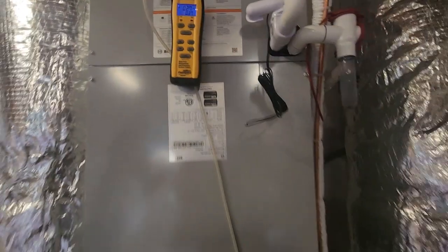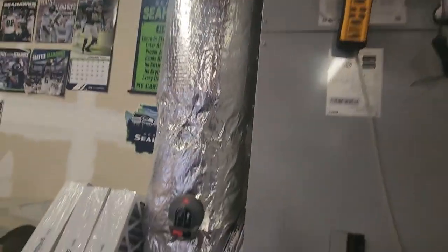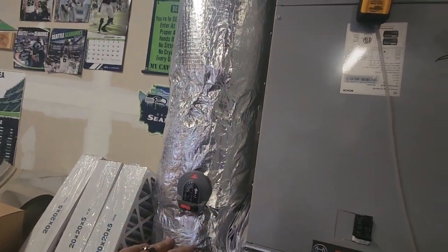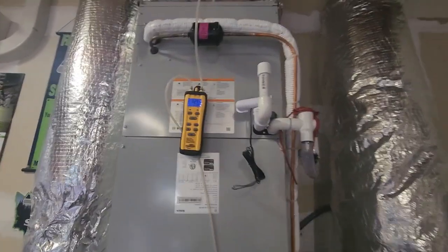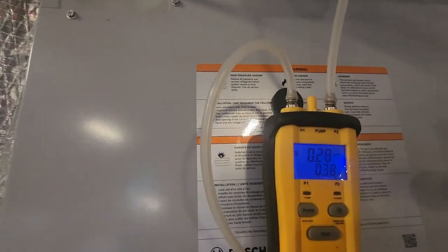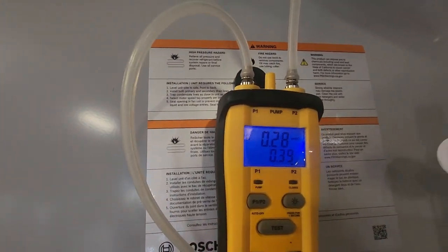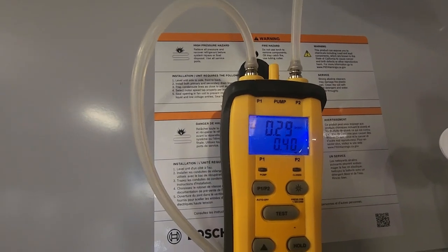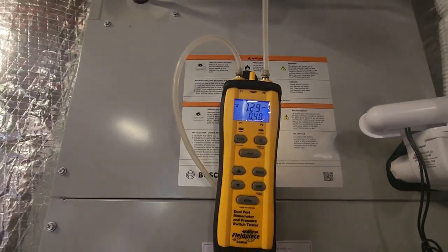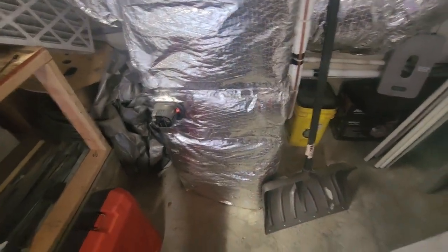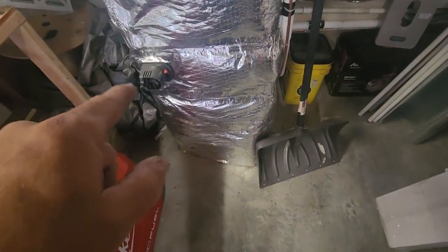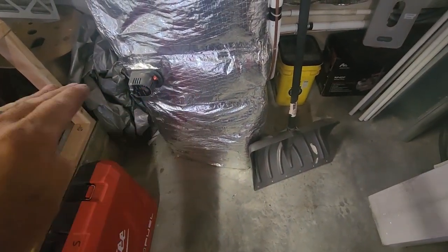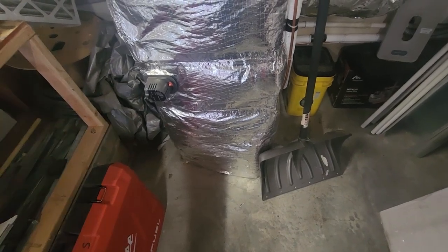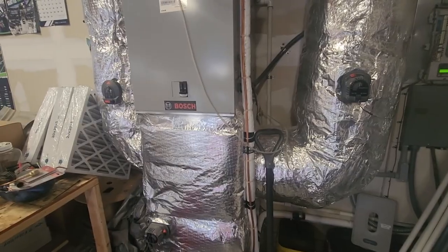Remember, I have both dampers open, and my bypass never opens, so it's always shut. This is just the system without the bypass. These are pretty awesome numbers. The downstairs zone I think is a little bit bigger, so let's shut it off and see what that does to our static.